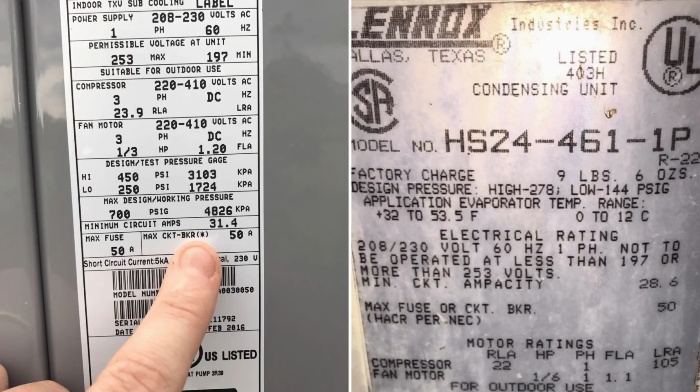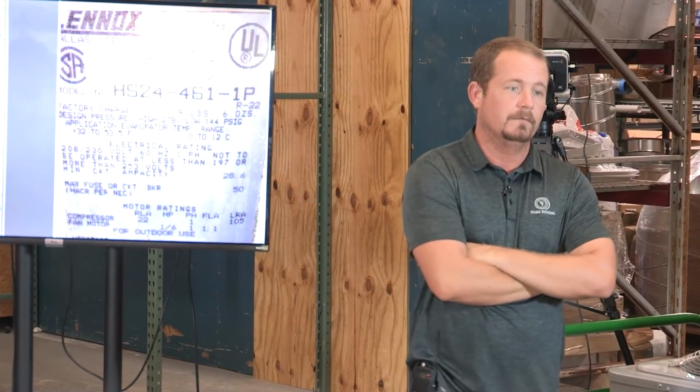All right, now here's where it starts to get really controversial. It's actually not controversial at all. It's super straightforward, and there should be no controversy. But it's a misunderstanding by electricians that results in this problem. So the saying that electricians repeat over and over and over again from the time that they leave the womb is that the circuit breaker is there to protect the conductor. Right? They'll always say that. The circuit breaker is there to protect the conductor.